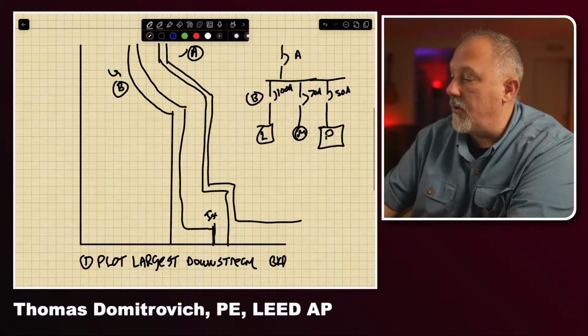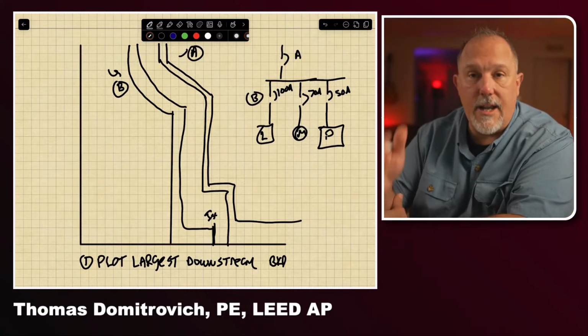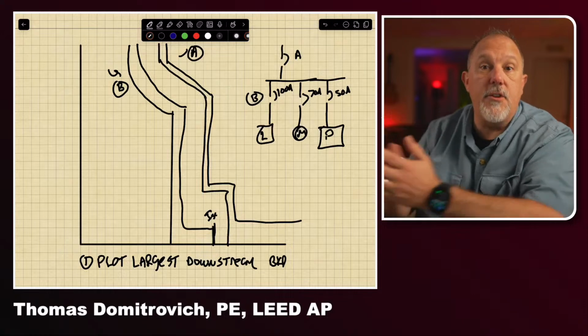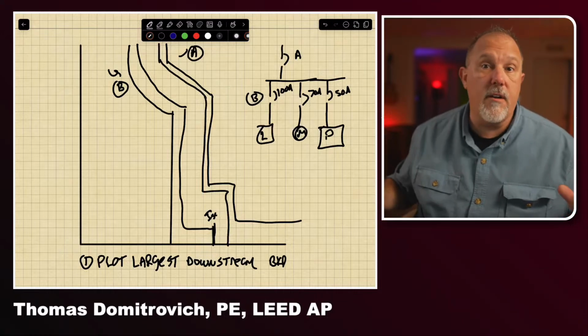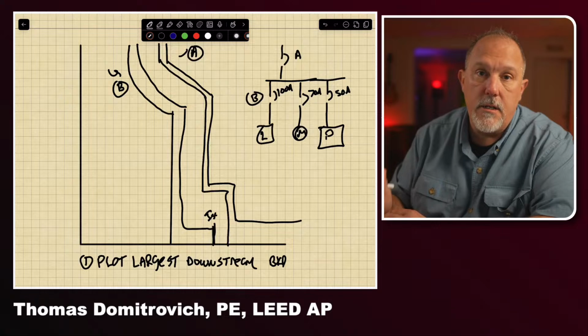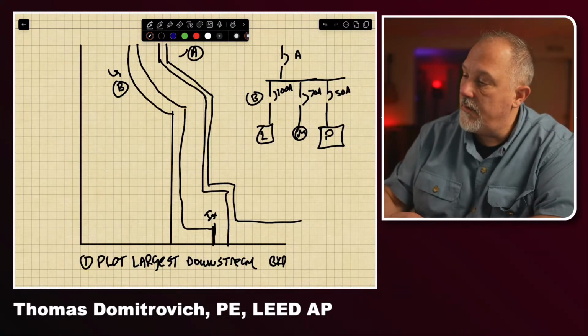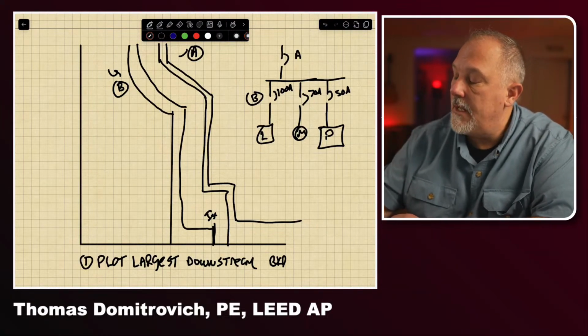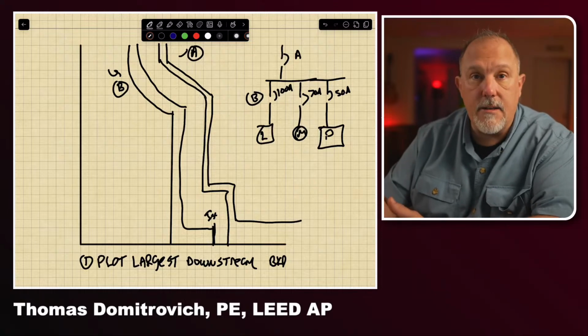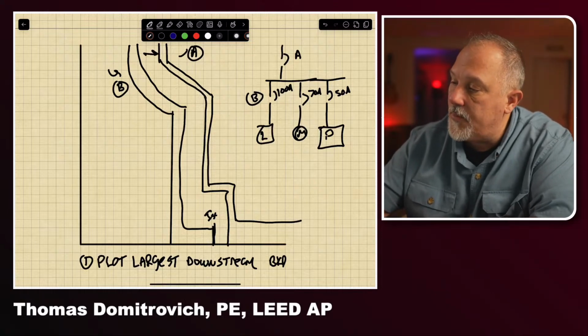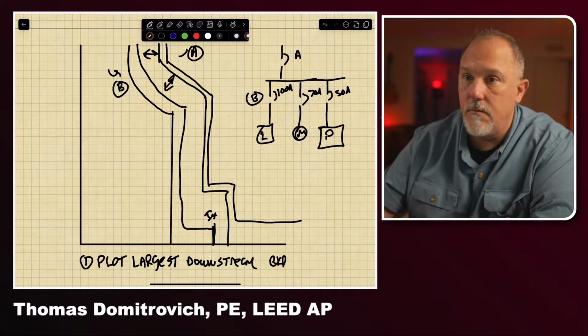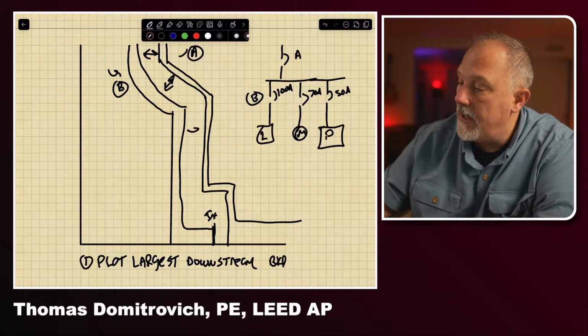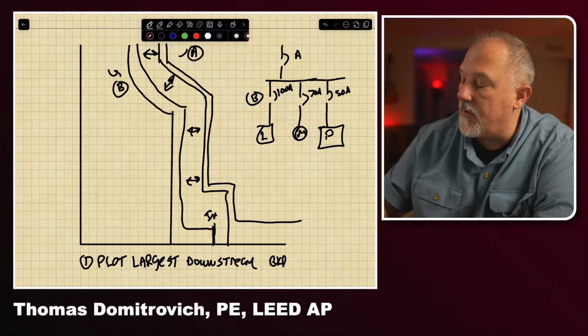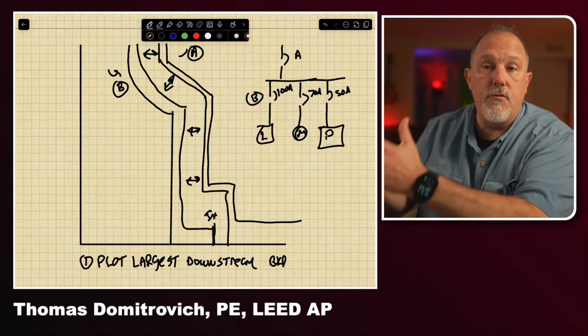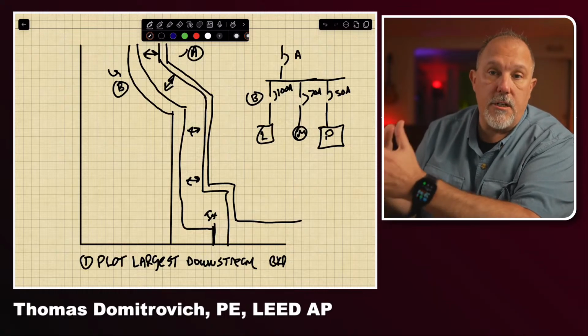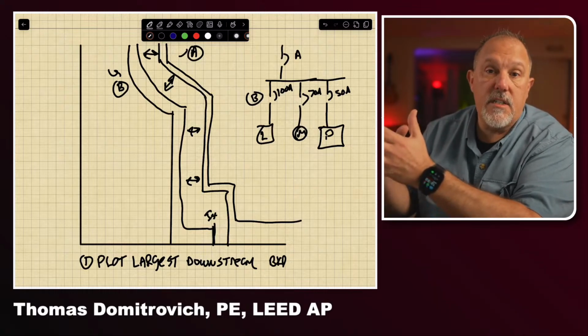So that's the first thing you do. If the largest downstream breaker works with everything upstream, then the smaller downstream breakers are going to work fine. But I would only plot the largest downstream breaker from A. Then I would plot A, and I would do that comparison. And I want separation in the overload region, so I'll have to verify that. In all of these regions, I can't have overlap because this is your overload region. That's your overload region of the system.